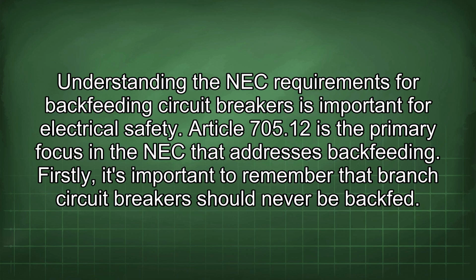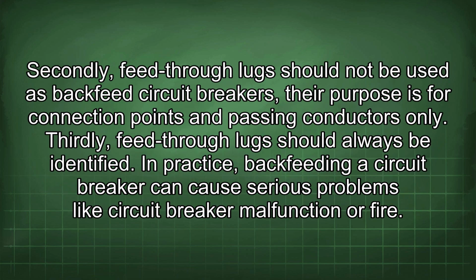Understanding the NEC requirements for backfeeding circuit breakers is important for electrical safety. Article 705.12 is the primary focus in the NEC that addresses backfeeding. Firstly, it's important to remember that branch circuit breakers should never be backfed. Secondly, feed-through lugs should not be used as backfeed circuit breakers. Their purpose is for connection points and passing conductors only. Thirdly, feed-through lugs should always be identified.